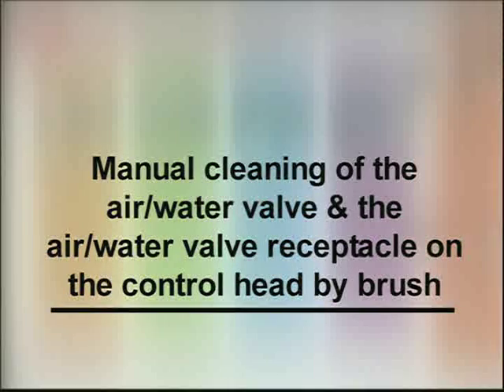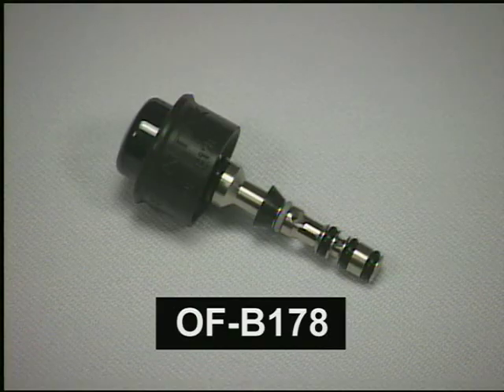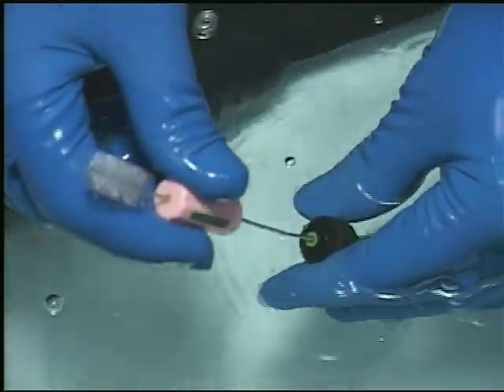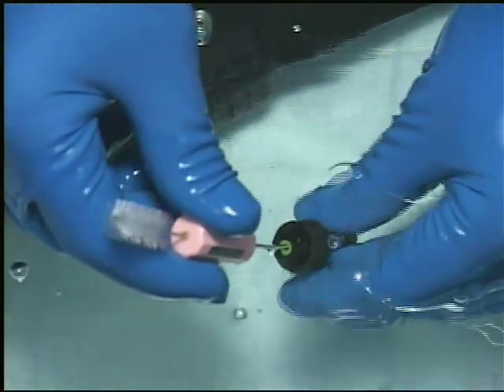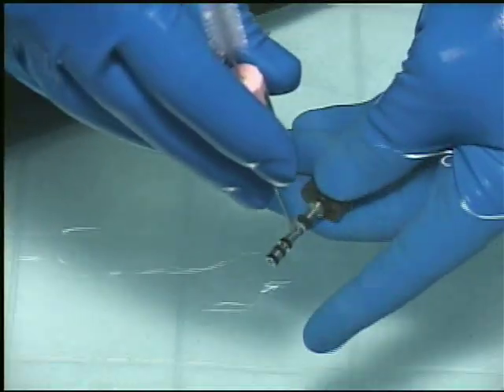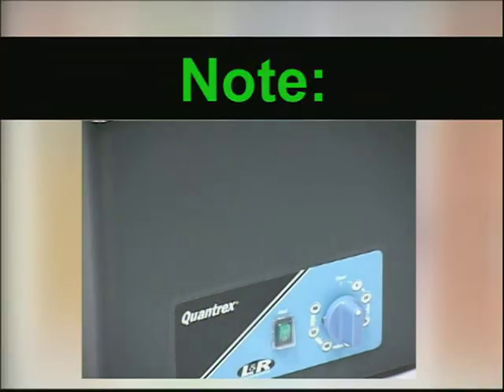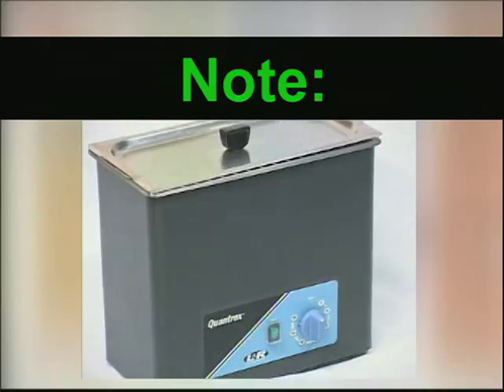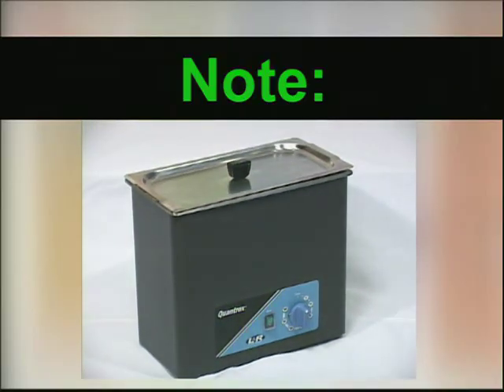Manual cleaning of the air-water valve and the air-water valve receptacle on the control head by brush. Remove the air-water feeding valve OFB178 and scrub all internal and external surfaces of the valve using the smaller side of the cleaning brush CSC8S. Note: ultrasonic cleaning is recommended for removable scope components and reusable accessories whose entire surfaces may not be easily accessible for manual cleaning, such as certain valves, inlet seals, etc.